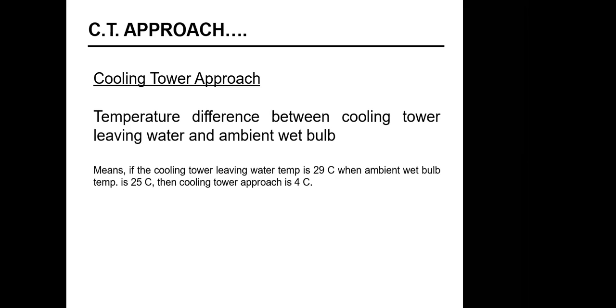Before that, I will just say, this is another technical term, called cooling tower approach. This term is used for the cooling tower. It indicates the performance of the cooling tower, that is, how effectively a cooling tower is able to reject the heat to the atmosphere, and it is basically measured using two parameters. One is the ambient wet bulb temperature and the other is the water temperature from the cooling tower. The difference between the two is called the approach. The smaller the approach, the smaller the delta T between the two, it means the cooling tower is operating at a very good performance level. The larger the delta T between these two parameters, it means its performance is not that great.